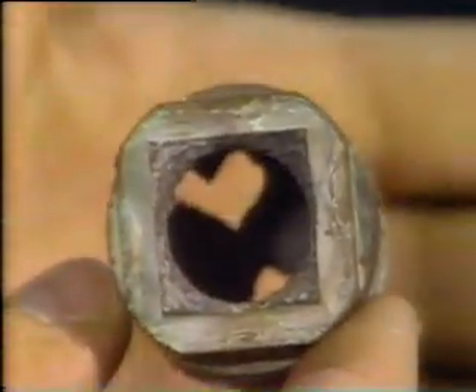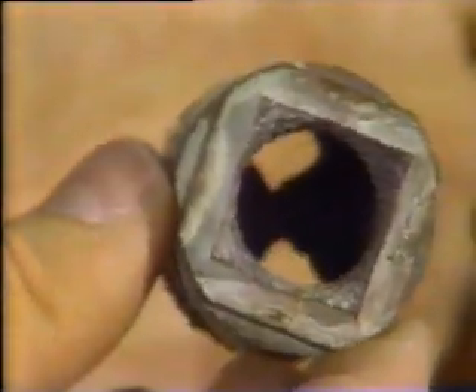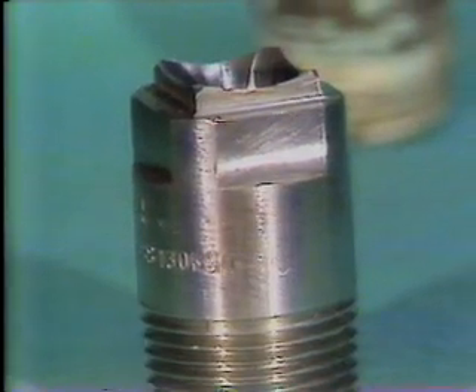Okay, now, where did we leave off? From time to time, your spray nozzles inside the evaporator might get clogged, generally because the scale or solids are getting past the sump strainer, or your nozzles might erode, like this one's done. Both cause the spray pattern to be affected, which will cause lower efficiency. Check through your inspection windows to ensure that the spray coverage is correct. If it's not, find out why and fix it. If you discover that the bronze nozzles in your unit have eroded, it'd be best to replace them with stainless steel nozzles. The bronze ones erode pretty fast.